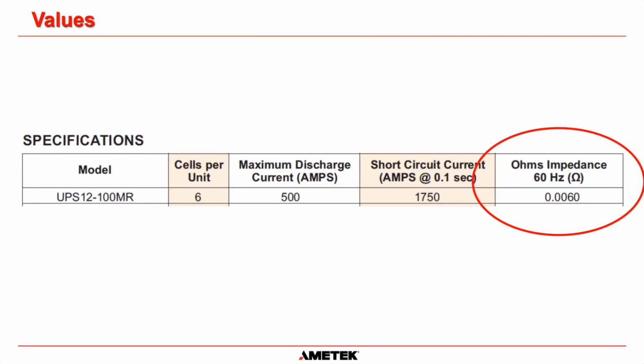And here's an example of a C&D battery. This is for a UPS 12100, and the manufacturer is telling us that the internal resistance of that battery, using a 60 hertz AC injection method, is 6,000 microohms or 6 milliohms. So that is an example of a battery manufacturer telling you what the baseline should be for that particular model of battery.